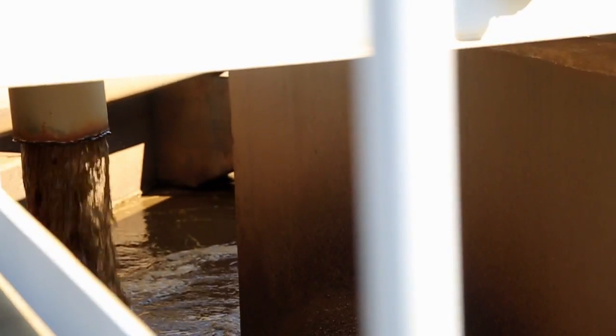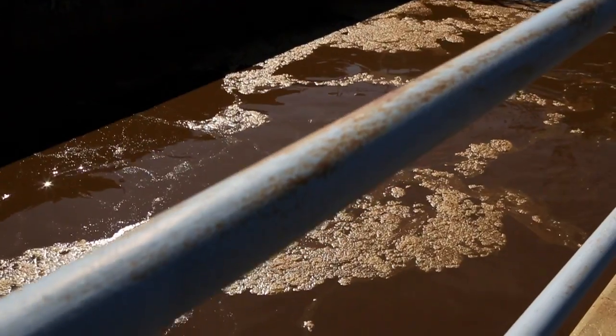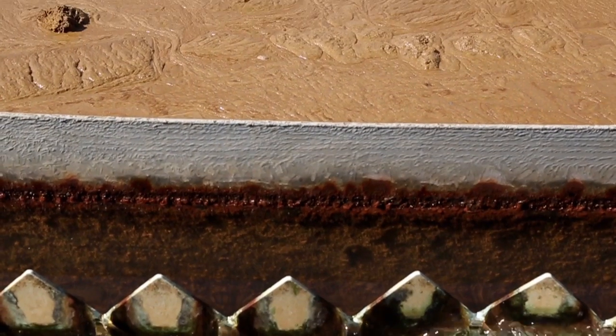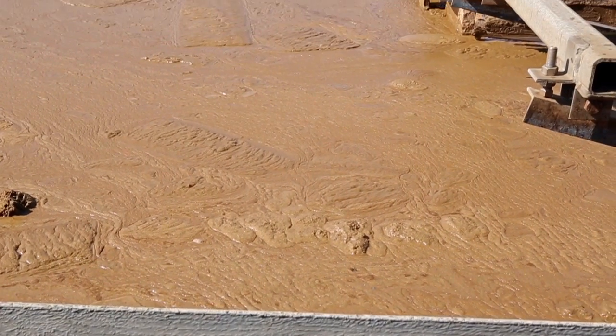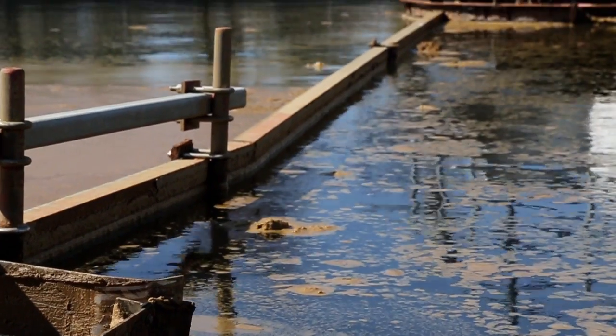In the winter we treat about 1 million gallons a day. The typical reaction when people come on tours and see this tank is, 'Oh my gosh, that's a whole tank full of fecal matter.' In reality it's not. The incoming wastewater has a TSS value of somewhere around 150 milligrams per liter. We maintain a biomass within this tank — a population of living organisms consuming the incoming wastewater. Following the biological portion is the sedimentation process, where the organisms settle to the bottom. The clear liquid remains on top, and a little bit of fats, oils, and greases floating on the surface is removed and sent out with the biosolids.